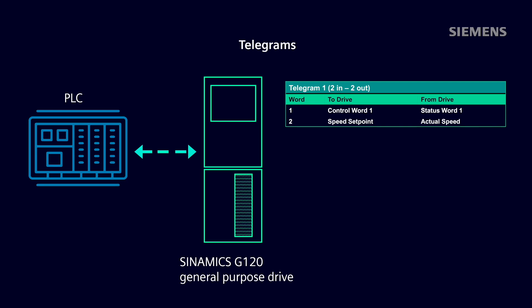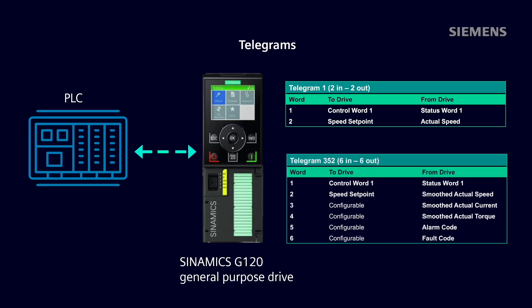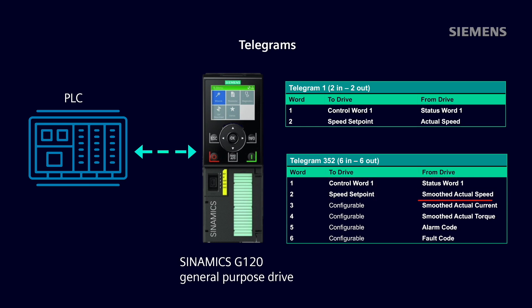The Siemens online support page for this application, linked in the description below, lists all of the add-on instructions for the different telegrams. For this demonstration, I will be using one of our most popular general-purpose drives, the SINAMICS G120, and I will use telegram 352, which is six words in length with drive control and status, speed setpoint and actual speed, actual current, actual torque, alarm code, and fault code.